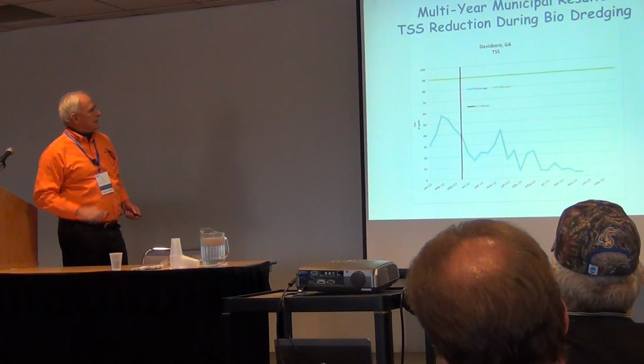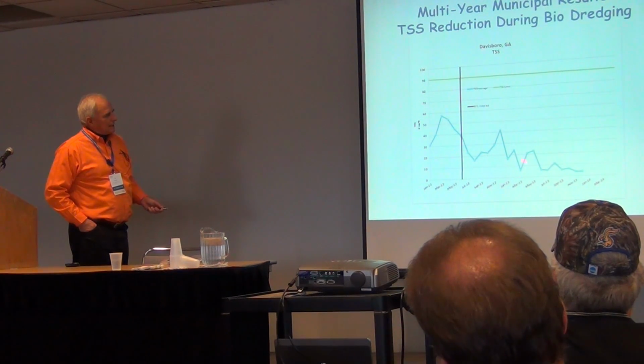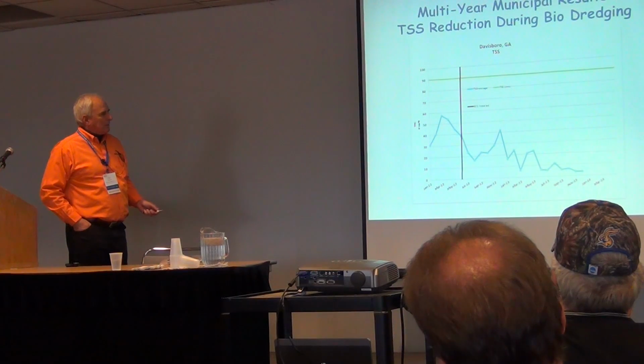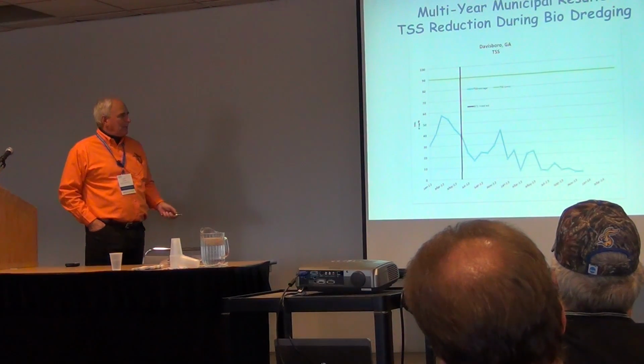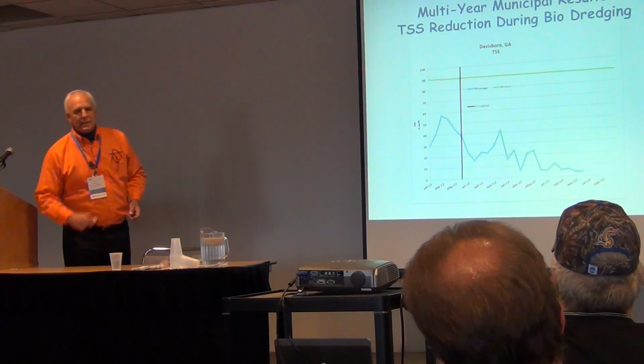So that's the BOD. This is the TSS. You see the same thing: this harmonic decay to a new lower equilibrium. Now, those of you with really good eyes would recognize that we're down to a single-digit BOD and single-digit TSS here.